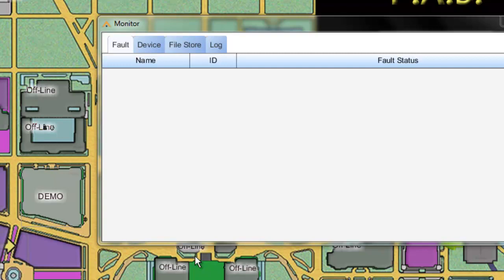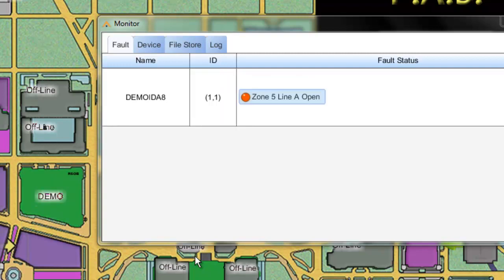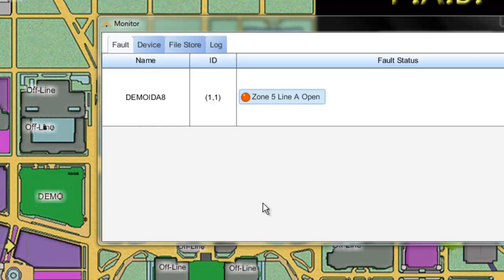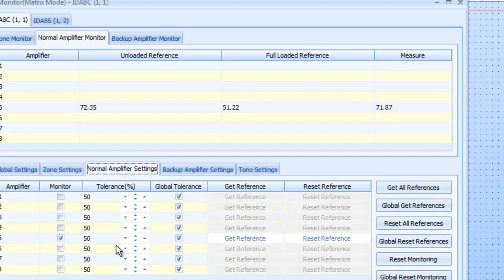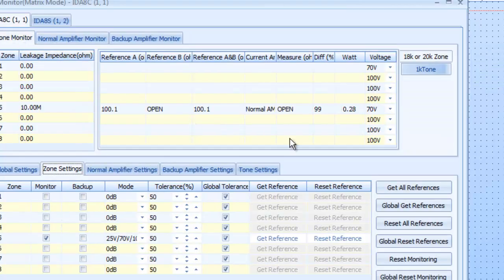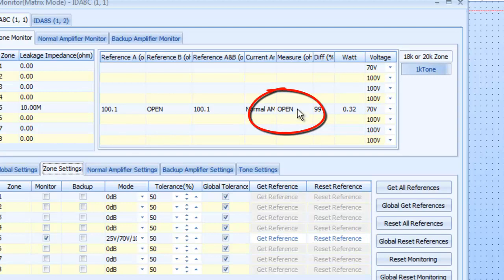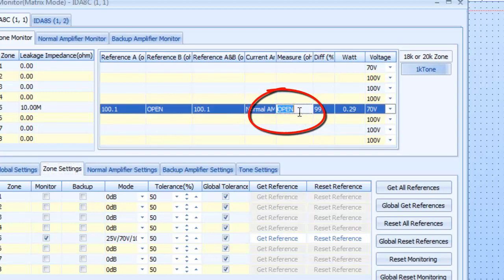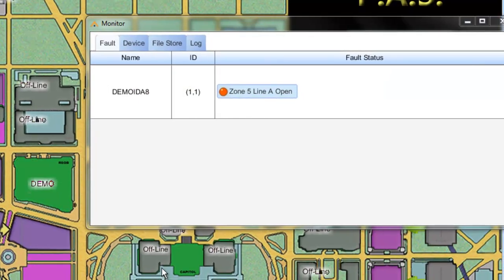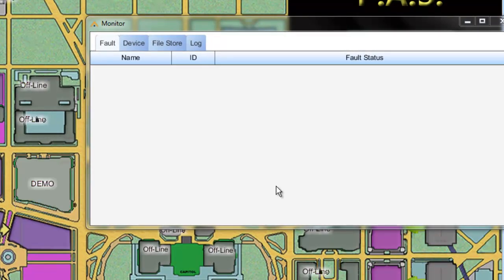So now it's cleaned up. Let's do the actual speaker output. I'm unplugging the 70 volt speaker output from zone 5 of the IDA8. Let's unplug now. There you go. We got our flashing red on zone 5. Line A is open. So that is good. If we go right to our monitor again. And we can show the difference is 99 percent. Because now the reference is 100. But now it's reading that the measurement on that line is open. And that is the problem. So let's go ahead and plug this back in. And you can see the measurements almost immediately. It comes up quickly. It measures it two or three times to make sure everything's back and stable. And as you can see automatically it goes away on the Terra Manager.